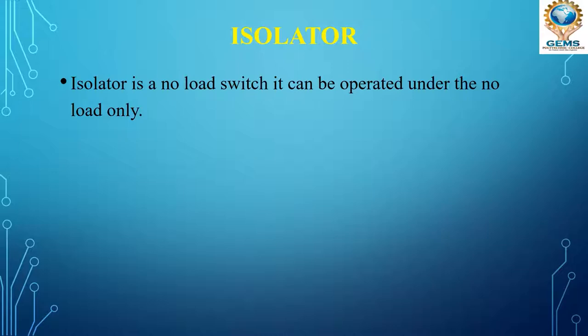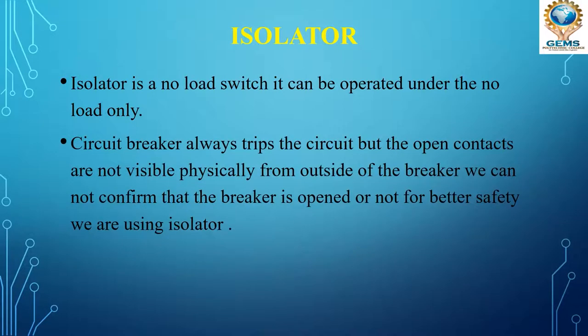Under no load conditions only we can use the isolator. If the load is on, we cannot operate the isolator. A circuit breaker always trips and opens the circuit, but the open contacts are not visible physically from outside the breaker, so we cannot confirm that the breaker is open or not.